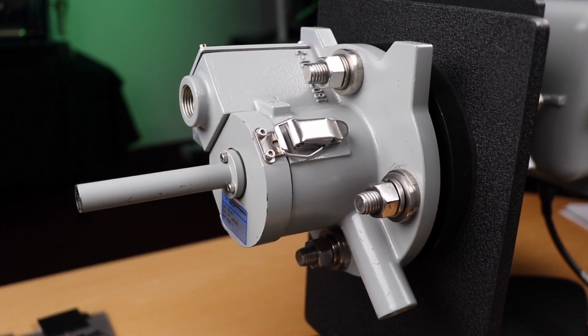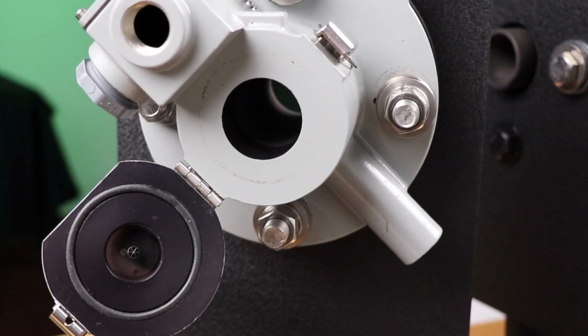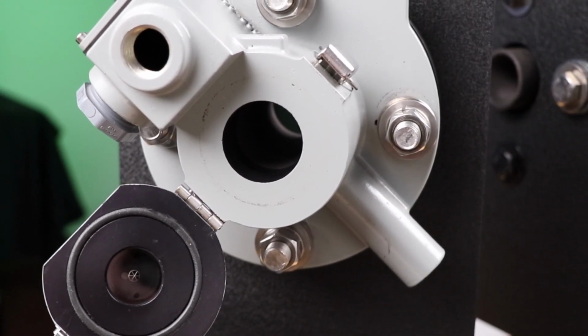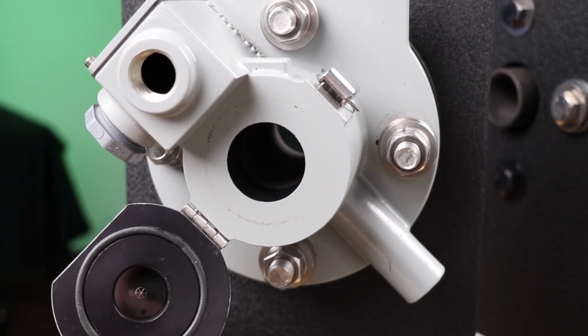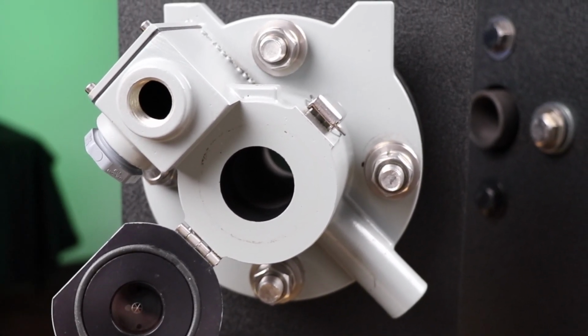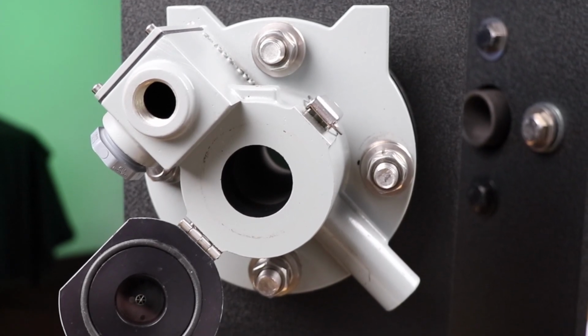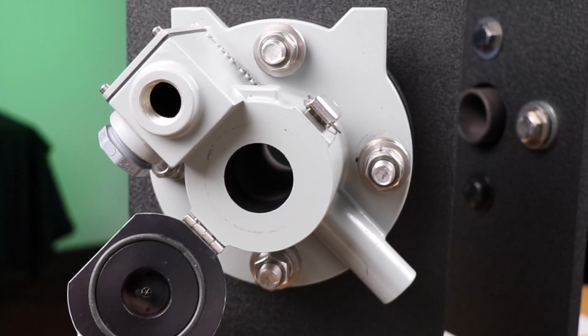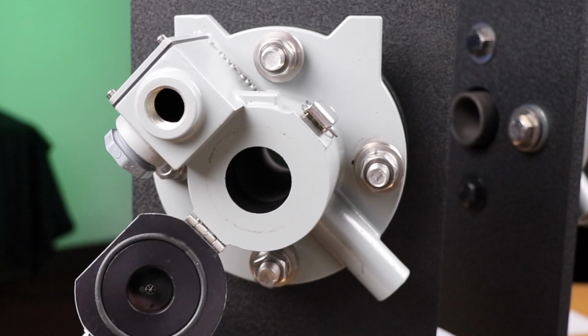The retroreflector assembly is mounted directly to the opposite side of the stack and concentrates the light beam back to the head unit. There are no electronics in the reflector, but rather one pressure microsensor and a relay for the purge air status returned to the head assembly.